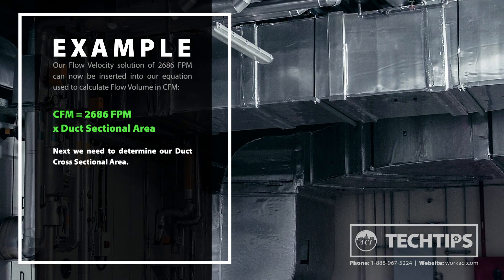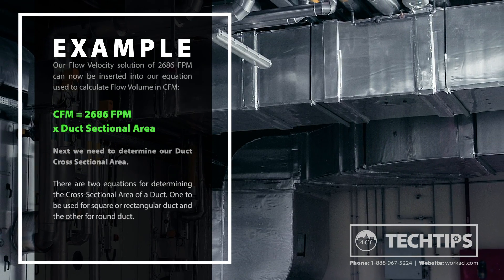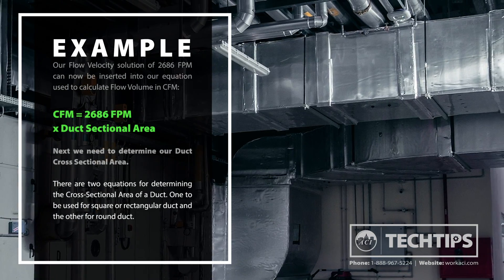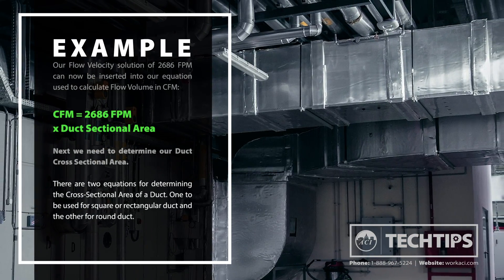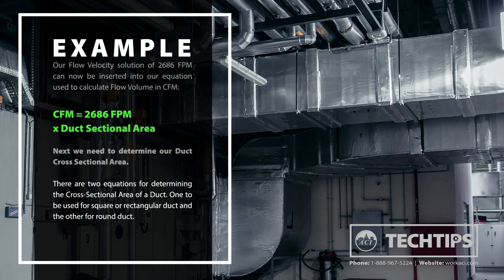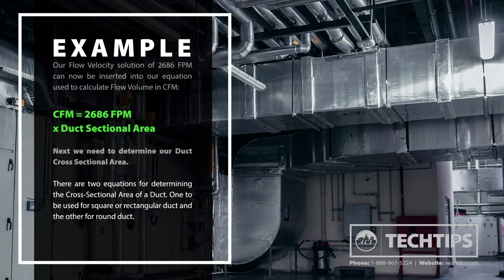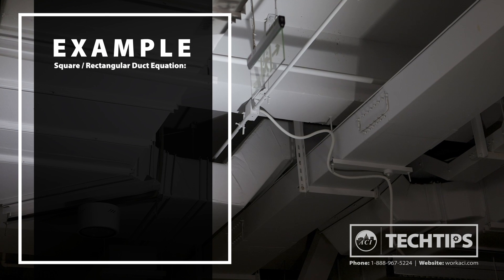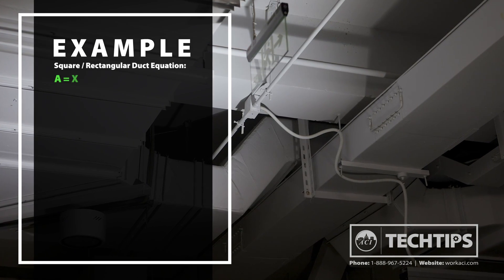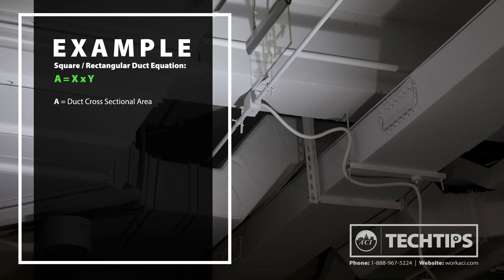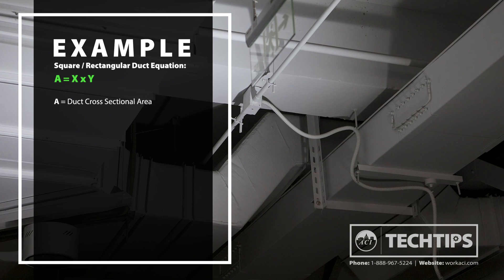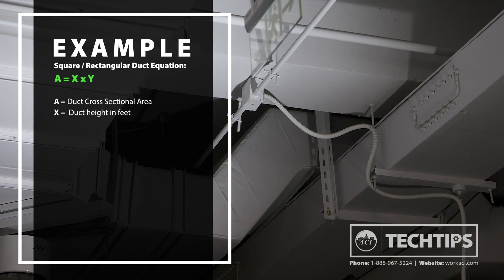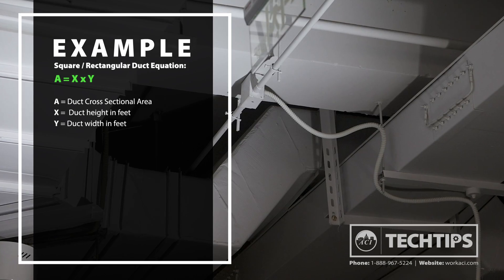Next, we need to determine our duct cross-sectional area. There are two equations for determining the cross-sectional area of a duct: one for square or rectangular duct and the other for round duct. The equation for square or rectangular duct is A equals X times Y — A being the duct cross-sectional area, X the duct height in feet, and Y the duct width in feet.